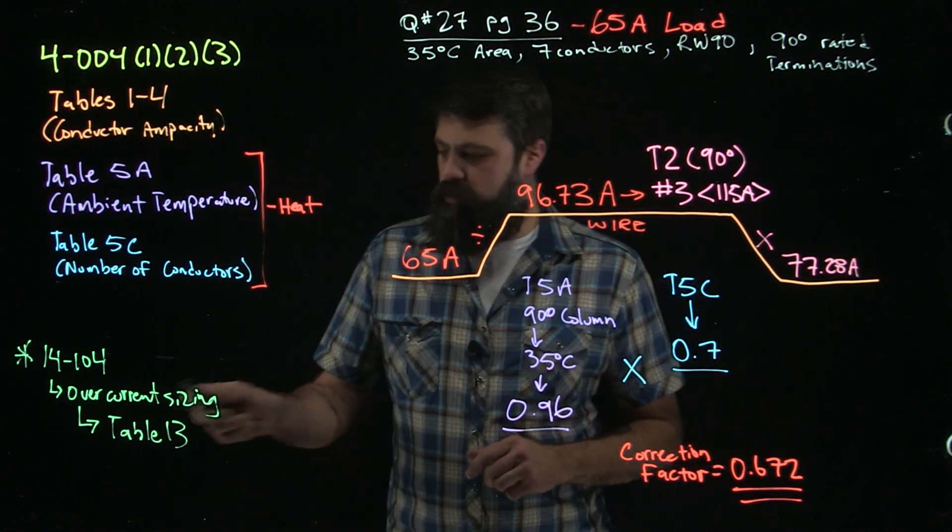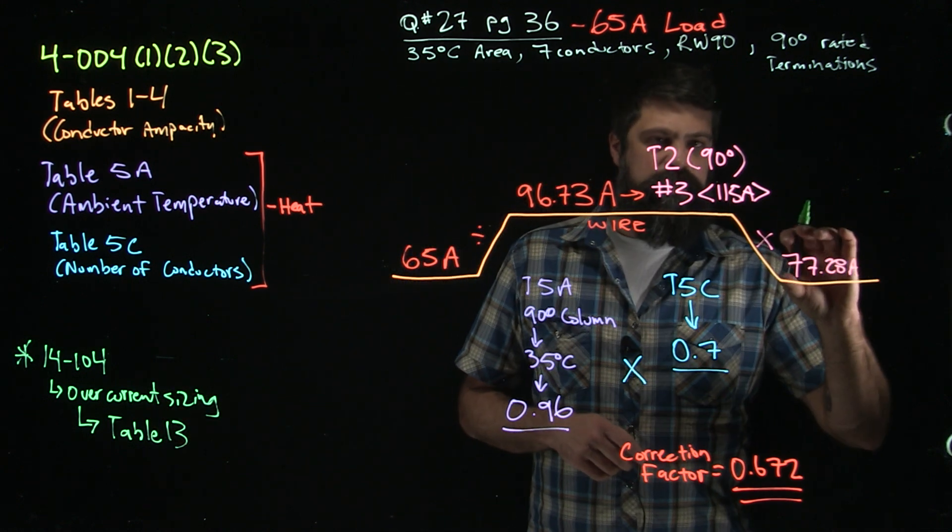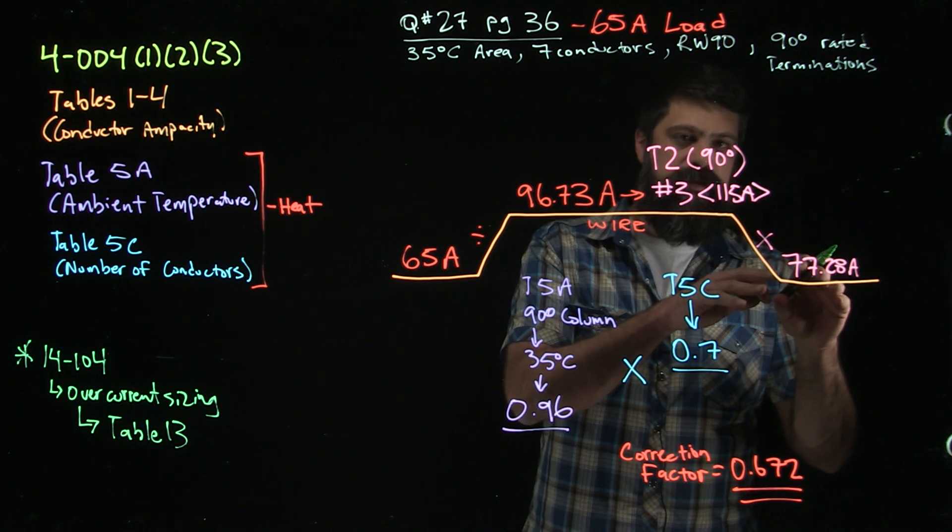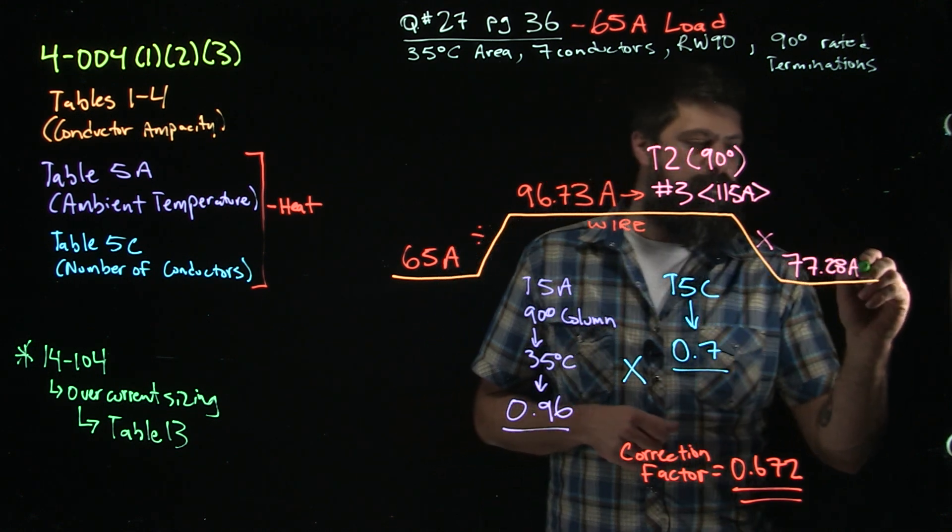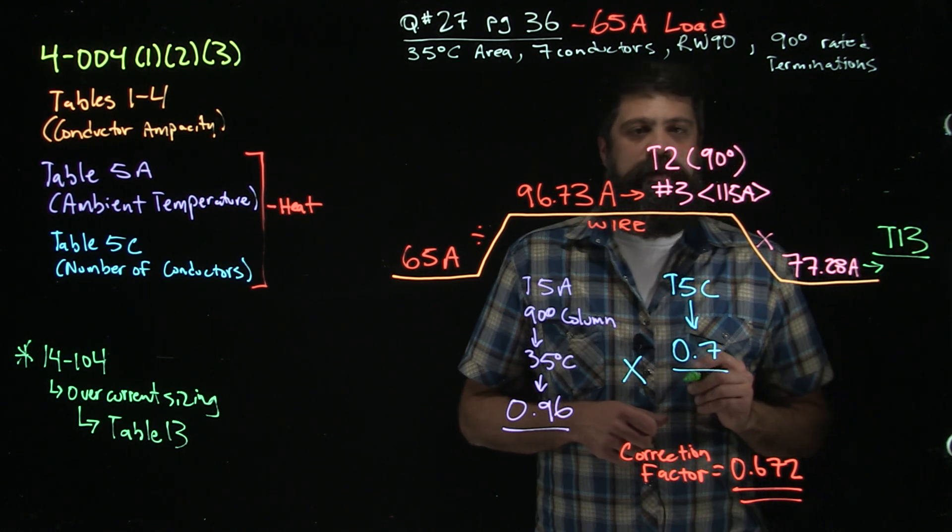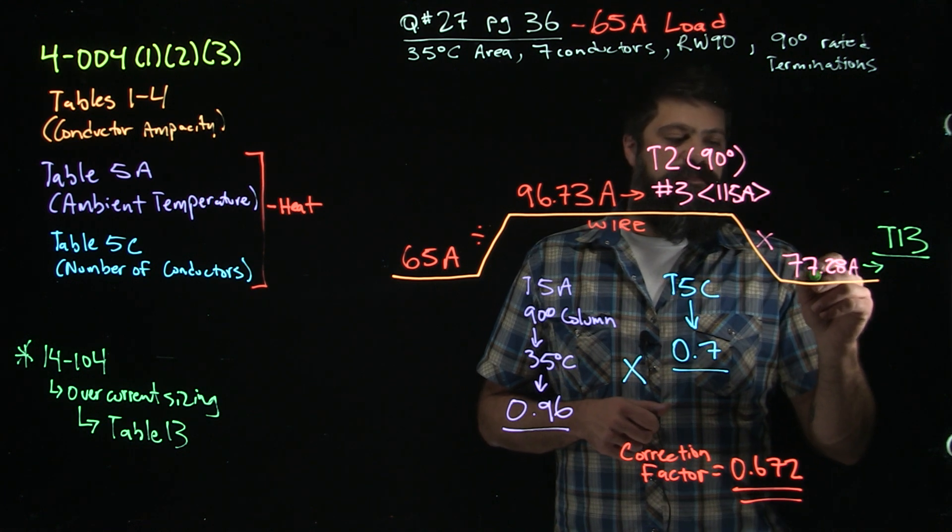Now, this is the number when we're using rule 14.104. What is the breaker there to do? The breaker is there to protect this wire. So under these conditions, 115 amp number 3 can really only handle 77.28 amps. That's what I'm sizing my breaker for.